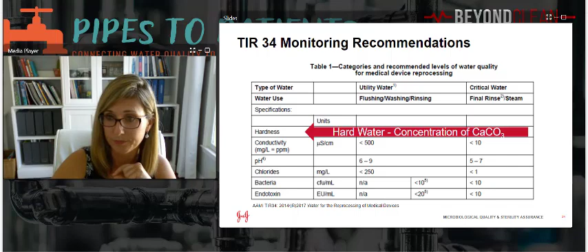The conductivity is in TIR 34 measured by resistivity, but in ST 108 it will be conductivity. It's just the measure of the water's capability to pass electrical flow, and it will be directly related to those ions in the water we talked about previously.